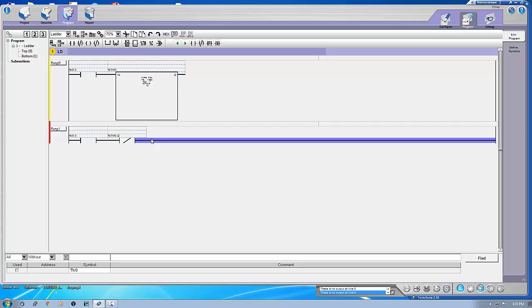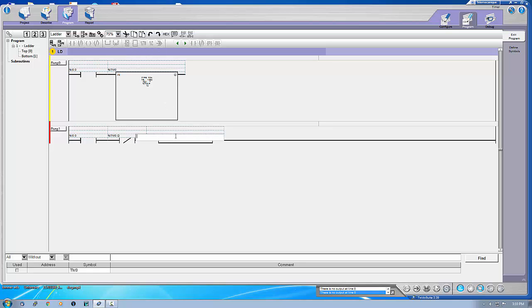Now we're using a comparator. What I want is for the first four seconds it should glow. But if I don't use the comparator, it would keep waiting till the Q bit is on, and only then the first output would glow. So for the first four seconds we need a comparator. Here's the comparator — %TM0.V stands for the accumulation of the timer. I want the first output to glow for less than or equal to four seconds.